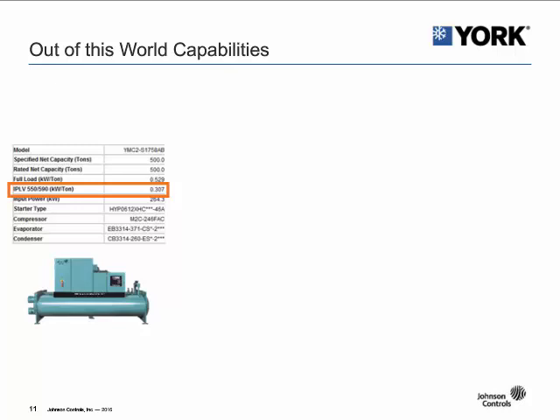Are the project economics you showed based on new construction? What about installing YMC² chillers as retrofits to replace WSE? Does that make economic sense at all? Again, if you already have the free cooling plate and frame heat exchangers, we didn't run that economic analysis within the study, but I can imagine that the plate and frame, if it can still provide some of the cooling tons to the building, does give some relief to the chiller, and the chiller can be used to make up the tons. But from a retrofit standpoint, there's confidence that both components will now work together in lieu of independent of how it was before.